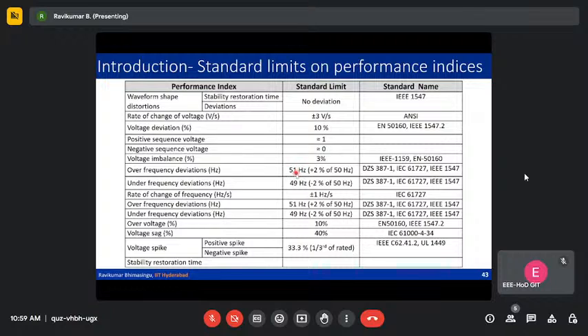Over-frequency and under-frequency deviations should be plus or minus 2% of the rated frequency, and over voltage should be limited to 10%. Voltage sag should be limited to 40% as per these standards, and spikes, positive or negative, should be limited to one third of the rated value. The stability restoration time should be as early as possible. These are some of the standard limits on performance indices, and they need to be met at any cost, so the system should perform very close to these limits.